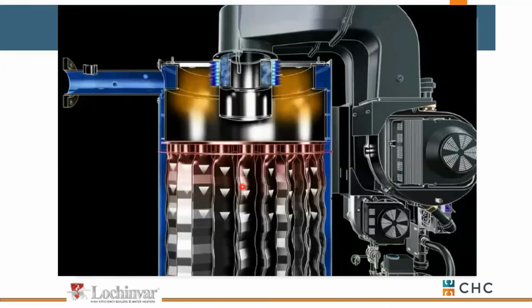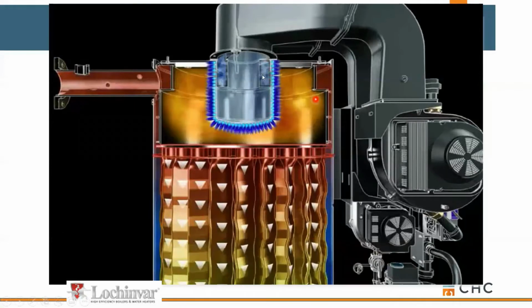Let's talk about how Lochinvar handles some turn down differences, or how they handle staging within their boiler design. When they first came out with this setup, they had 2 blowers, a small blower and a very large blower, and each one of these has a gas valve that goes along with it. They've got a 2-chamber burner design, so the small burner here handles loads from 5 to 20%. If 20% doesn't meet the hot water requirements for our building, then we open up the second gas valve, fire the second blower, and now we control from 20 to 100%, firing the whole burner. Okay, so it's kind of a 2-stage setup.